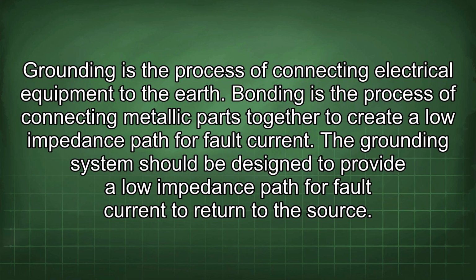Grounding is the process of connecting electrical equipment to the earth. Bonding is the process of connecting metallic parts together to create a low impedance path for fault current. The grounding system should be designed to provide a lower impedance path for fault current to return to the source.